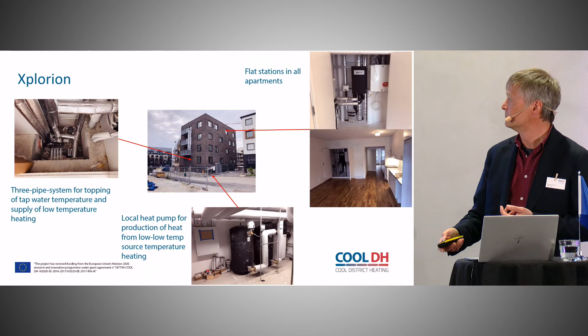Another thing we've tested within the project, again a Logstar innovation: it's an ordinary district heating pipe with a steel pipe in the center, but there are two odd pipes on the side. The aim is to recover heat lost from the district heating piping back into the heating system. This is done by keeping the temperatures in the side pipes very low, so the heat loss ends up there. We've also installed a heat pump at a customer that increases the temperature of the recovered heat — so no heat losses, and possibly some extra heat taken from the surrounding ground.